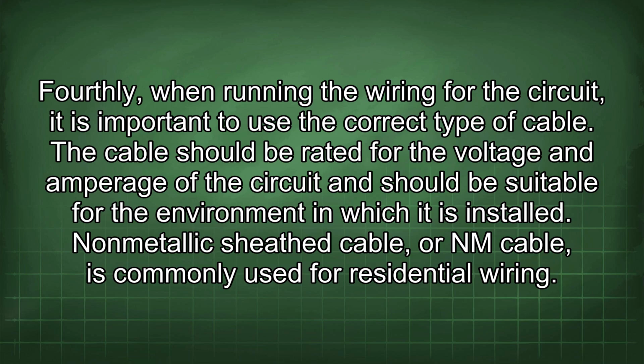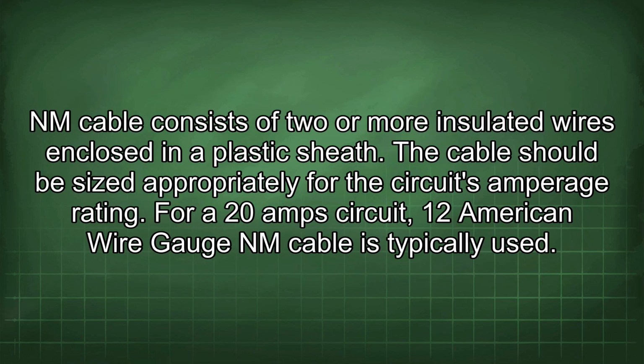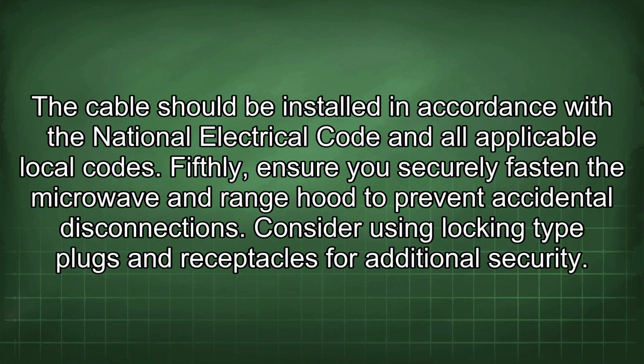Fourthly, when running the wiring for the circuit, it is important to use the correct type of cable. The cable should be rated for the voltage and amperage of the circuit and should be suitable for the environment in which it is installed. Non-metallic sheath cable, or NM cable, is commonly used for residential wiring. NM cable consists of 2 or more insulated wires enclosed in a plastic sheath. A cable should be sized appropriately for the circuit's amperage rating. For a 20 amp circuit, 12 American wire gauge NM cable is typically used. The cable should be installed in accordance with the National Electrical Code and all applicable local codes.